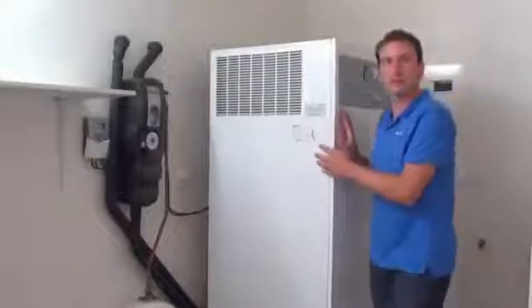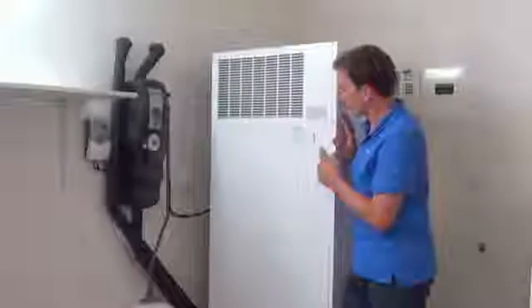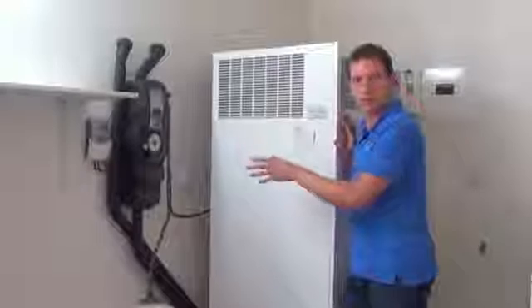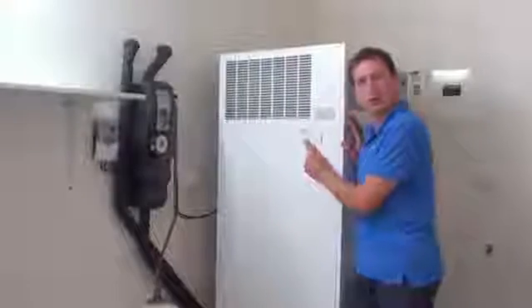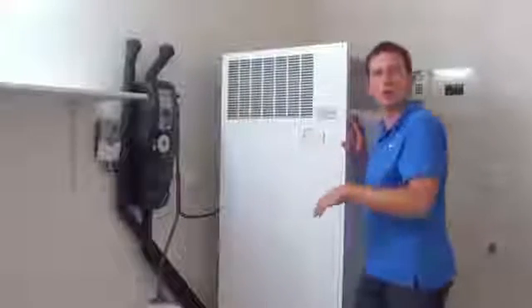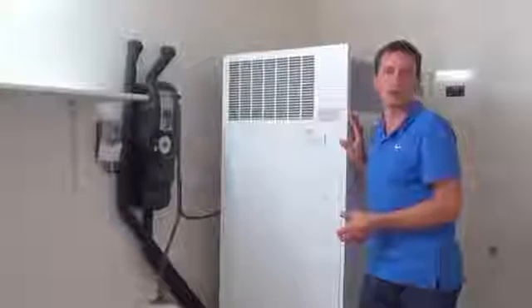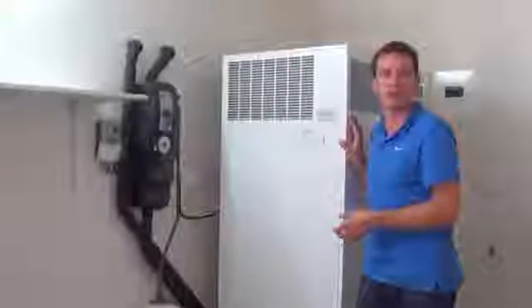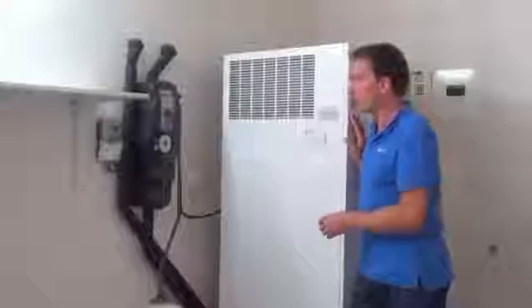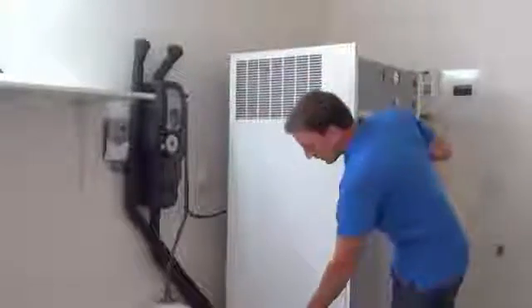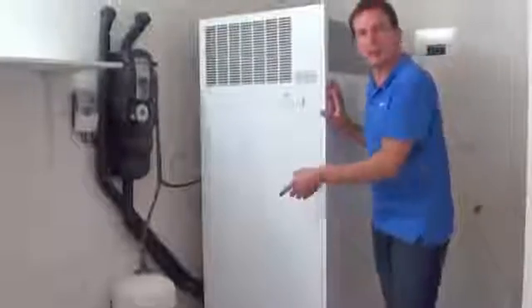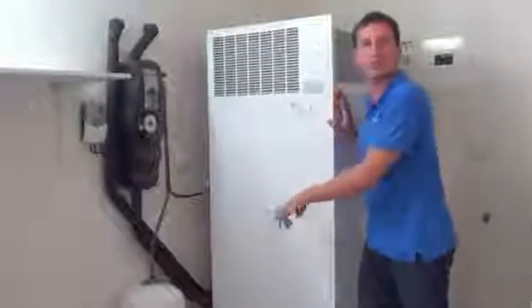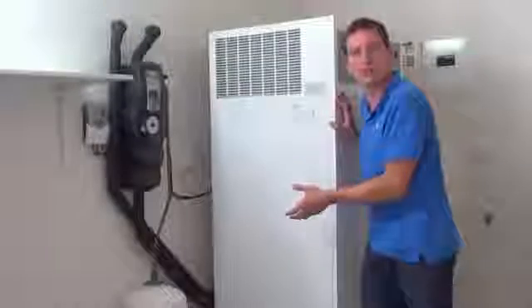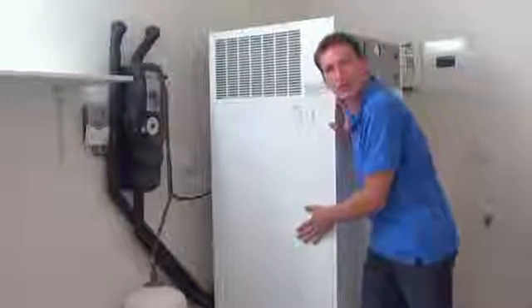Okay, to make the system even more economical, we have combined it with solar to save on that 0.44 kilowatt that this client's using. He wanted to go away from Eskom as far as possible, or to go away from consuming any energy, and this is as close as we could come. We've supplied a solar panel with a heat exchanger already pre-built in here from the manufacturer. They've actually welded it into the tank, and they've put the enameling process over the heat exchanger and the tank on the inside.